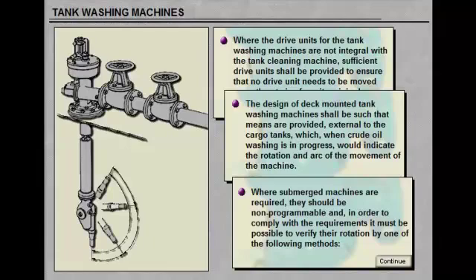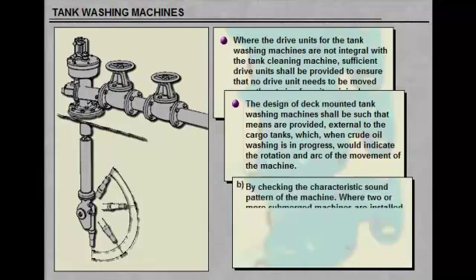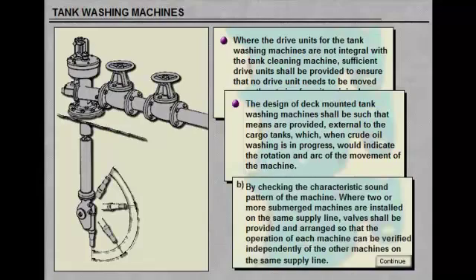A, by indicators external to the tank. B, by checking the characteristic sound pattern of the machine. Where two or more submerged machines are installed on the same supply line, valves shall be provided and arranged so that the operation of each machine can be verified independently of the other machines on the same supply line.